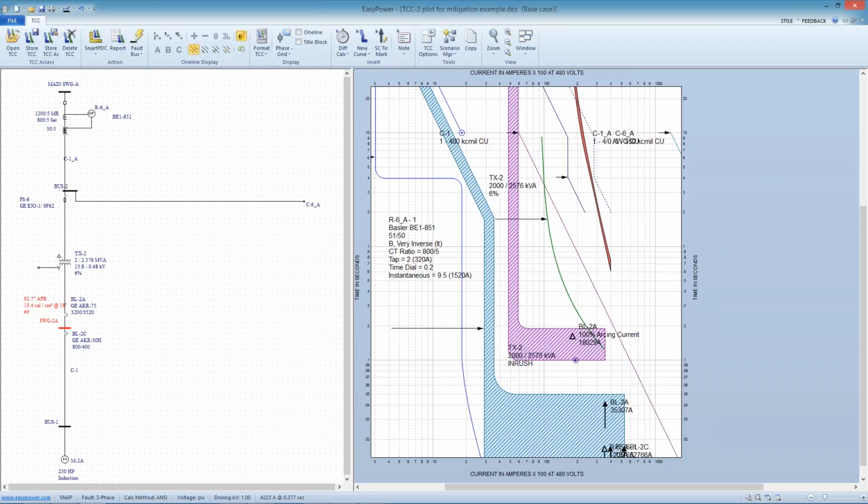Did that make sense? So I was able to lower this somewhat, even though there wasn't an indication that it was even in the circuit, and by the way, it was originally set. Now that's the kind of thing that may have occurred with somebody tweaking the relay settings.